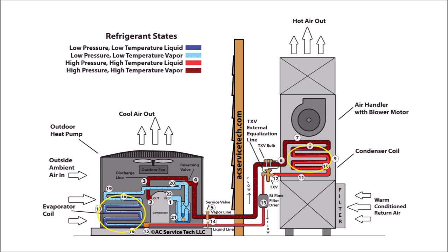Anytime you see two colors inside the tube at the same time — one being a liquid and one being a vapor — that means the refrigerant is in the saturated state. At step one, we have the low pressure, low temperature, superheated vapor entering the vapor compressor. At step two, we have the high pressure, high temperature, superheated vapor exiting. Remember that the compressor increases pressure, which therefore increases temperature. At step three, we have the high pressure, high temperature, superheated vapor traveling through the discharge line and heading towards the reversing valve.